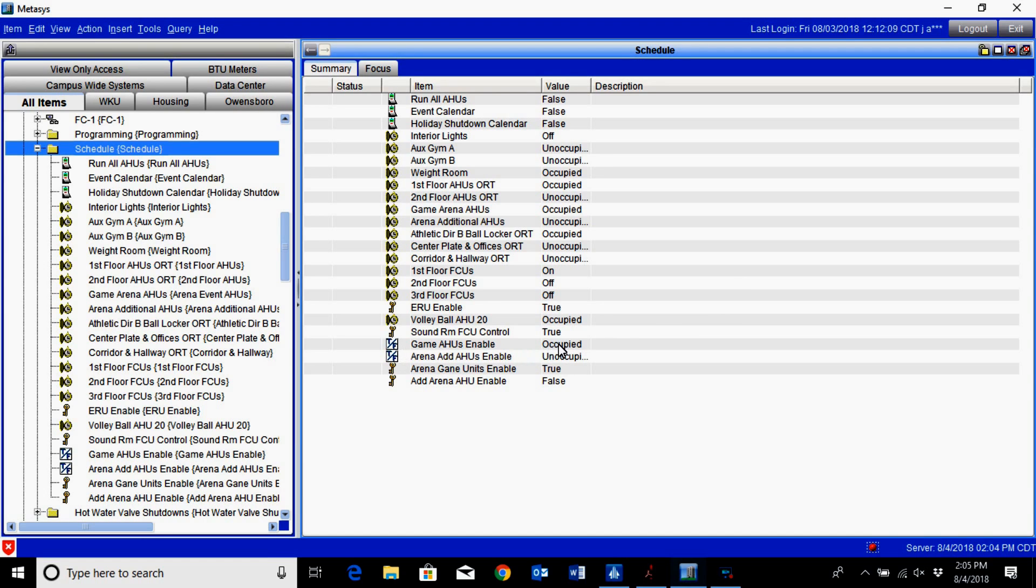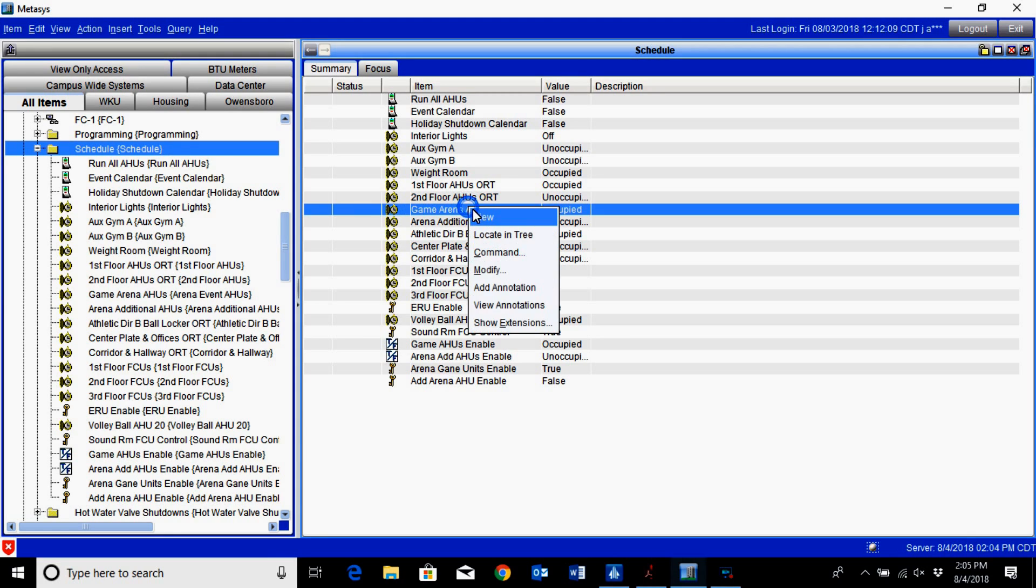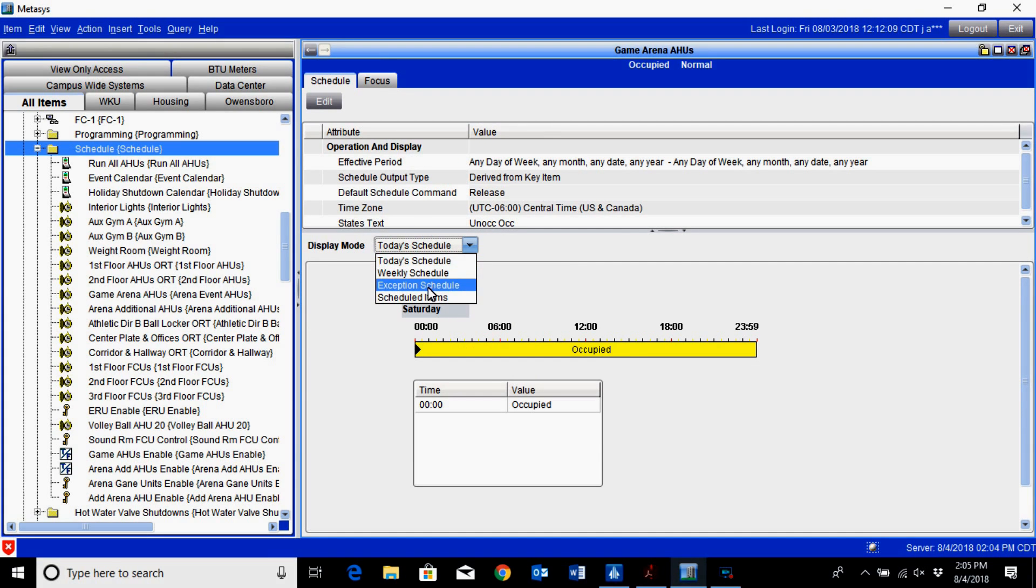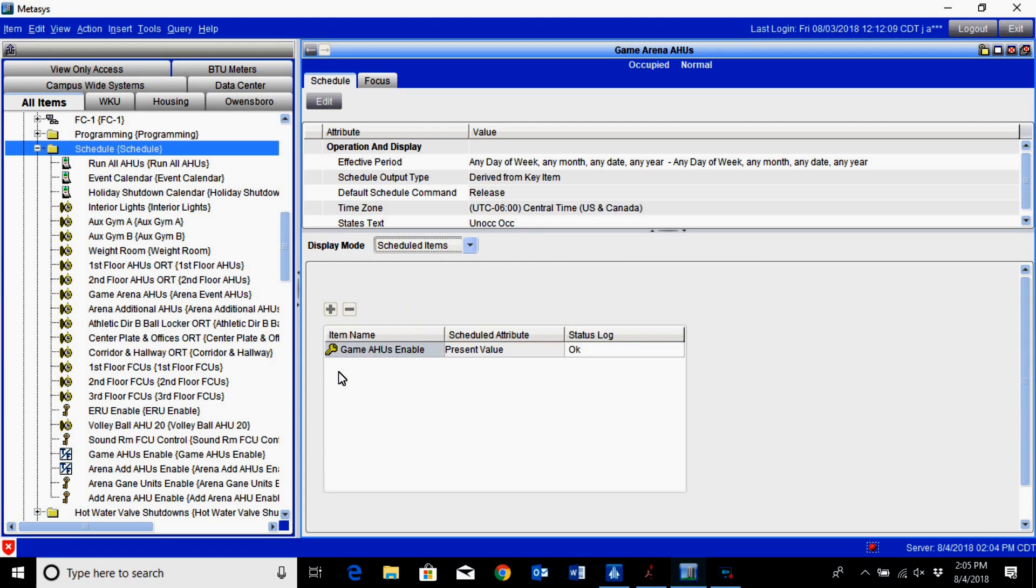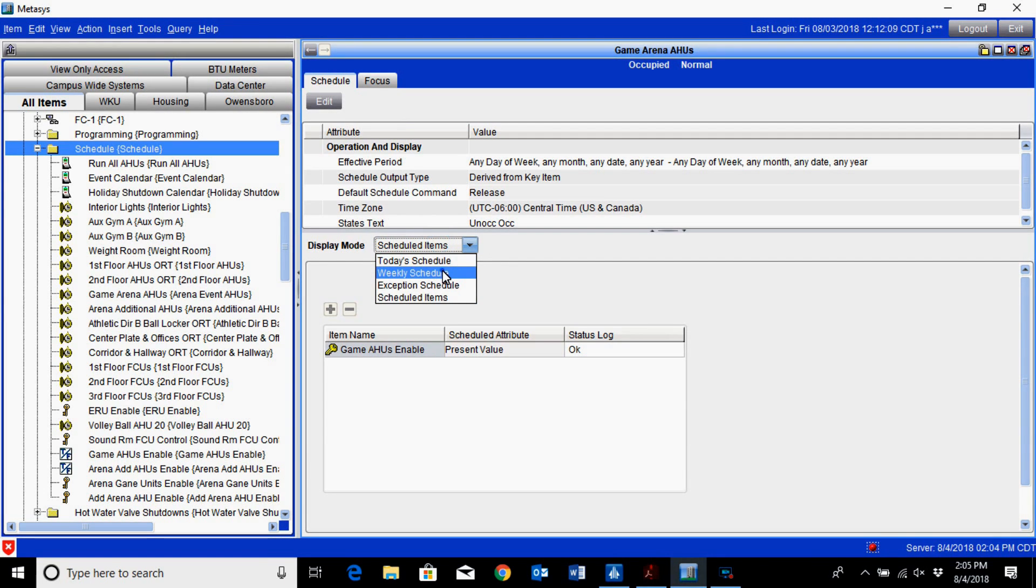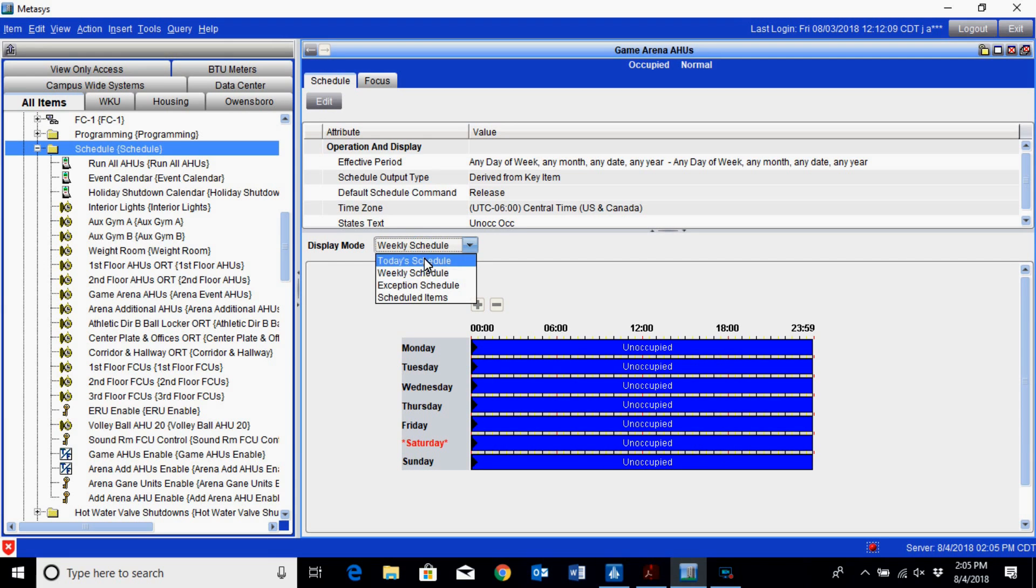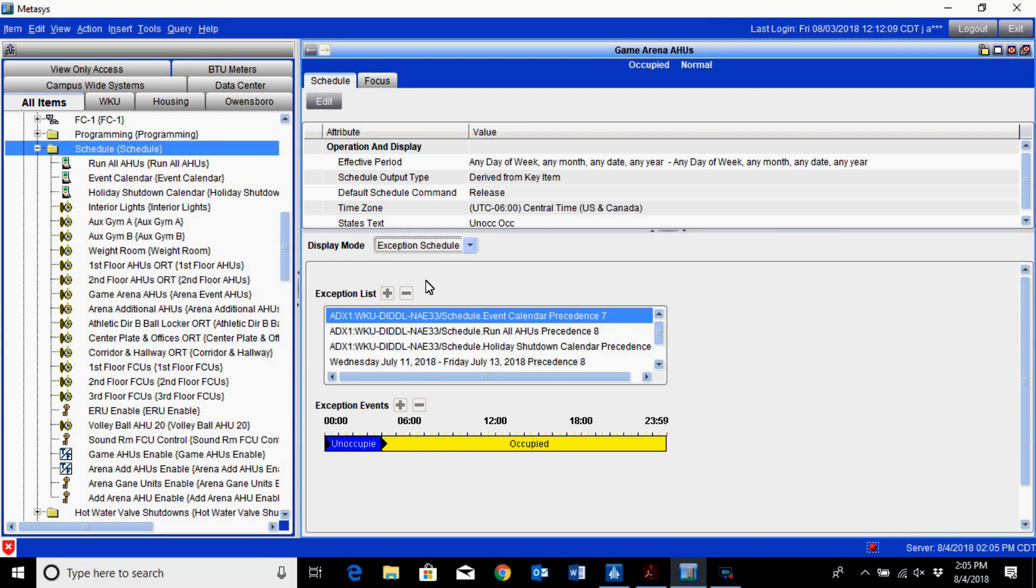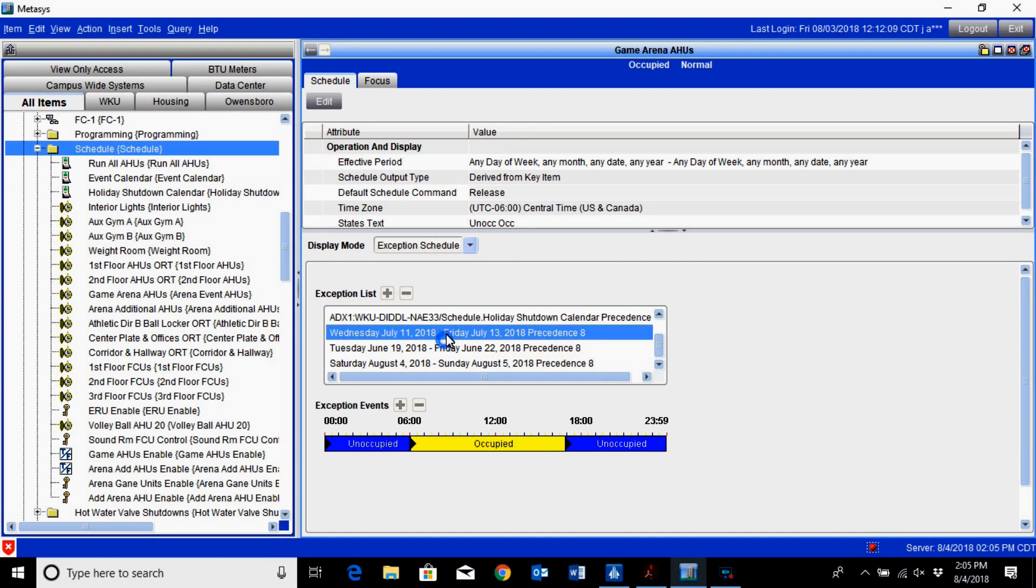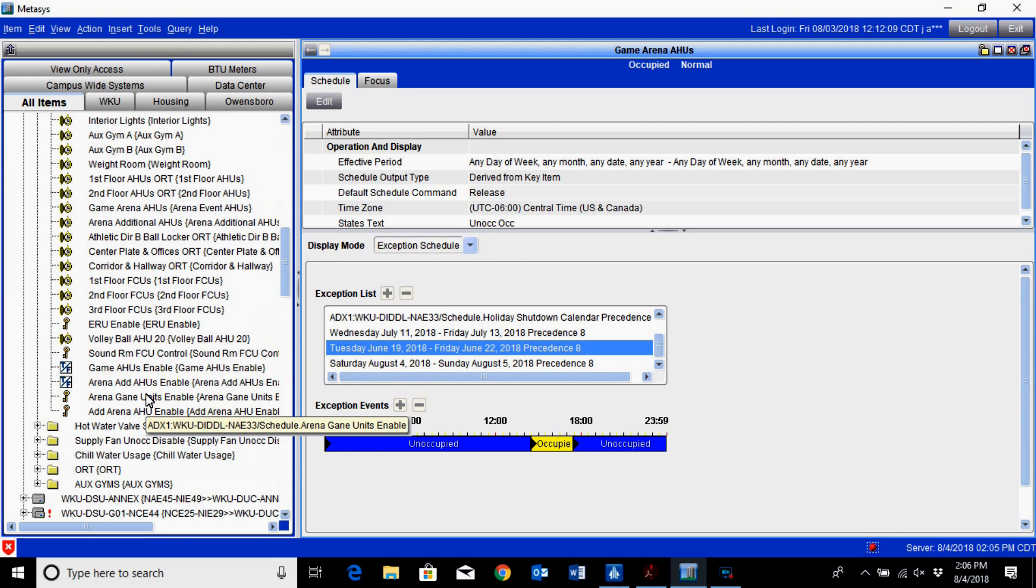The game arena air handlers, this point here is just a binary value that is occupied. What we do is take our schedule here and simply add that game arena object to our schedule right here. This is our weekly schedule since we only use this during events, and you can go in and set up your exception schedules for whenever it is needed.